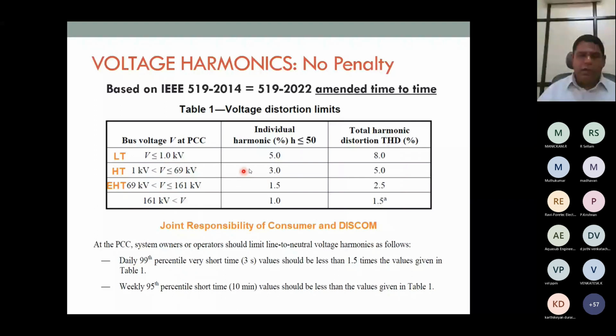So individual harmonic is the individual order harmonics. For HT consumers, they have to maintain 3%. If it is the fifth harmonic, the limit will be 3%. And for the total harmonic distortion, it will be 5%. So it will be a joint responsibility of the consumer and the DISCOM. DISCOM is nothing but the electricity board. So at PCC, the system owners should limit line to neutral voltage as follows, 99%. This I'll explain to you in detail in the next slide.